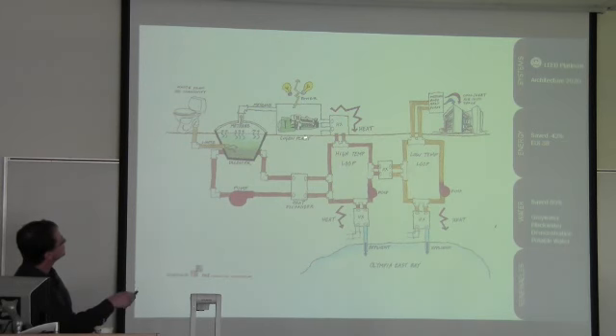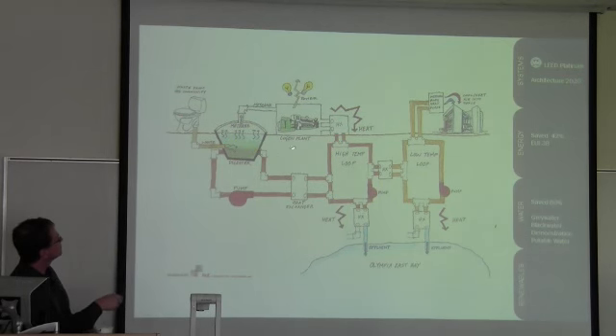It used to be that this was the location for the boiler. We'd take the methane right through the boiler and it would go into a high temp loop and that would feed back into the digester. So we took that out and we put a cogeneration plant there, basically an engine-driven generator. And we take the waste heat from the generator and we run that through the high temp loop to do the process that it needs to do with the digester. But then we also share that heat with a lower temp loop, which actually acts like a condenser water for our building. And it serves the heat pumps in the space.